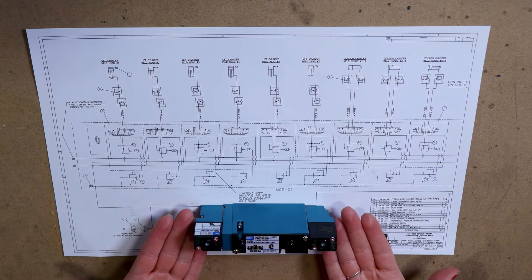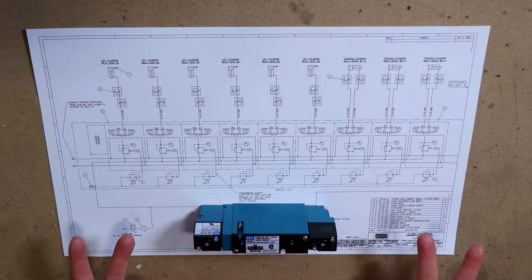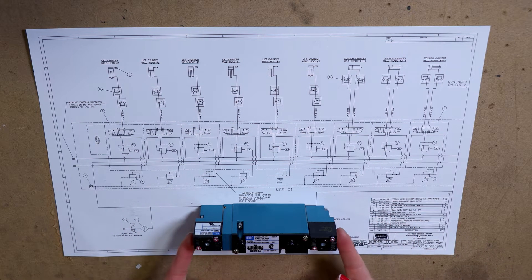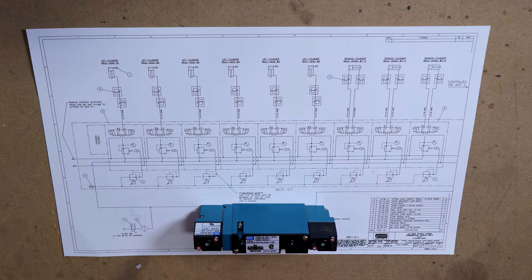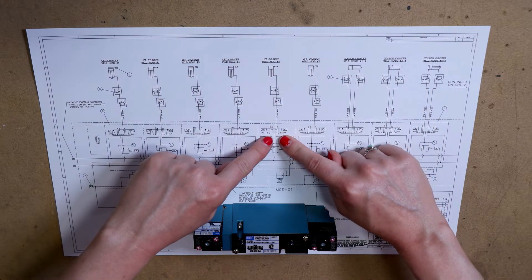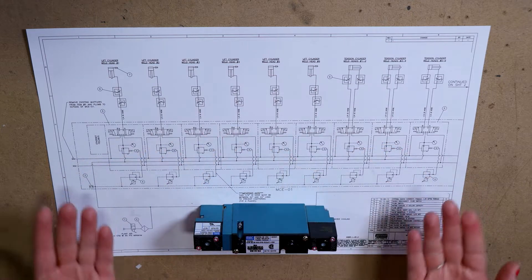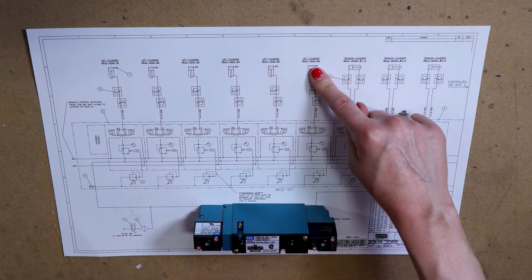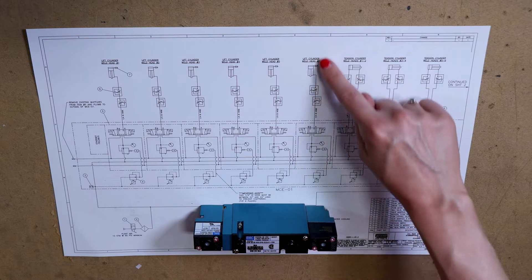Three-position allows the valve to be energized in two separate directions by two separate solenoids, solenoid A and solenoid B. This will then allow the air to flow through one port and exhaust out another, thus allowing the cylinder that is connected to the valve to move back and forth.